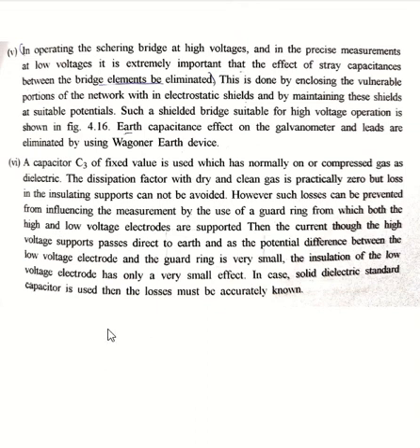The capacitor C3 of fixed value is used, which normally has oil or compressed gas as dielectric. The dissipation factor with dry and clean gas is practically zero, but loss in the insulating support cannot be avoided. However, such losses can be prevented from influencing the measurement by the use of guard rings, from which both the high and low voltage electrodes are supported.